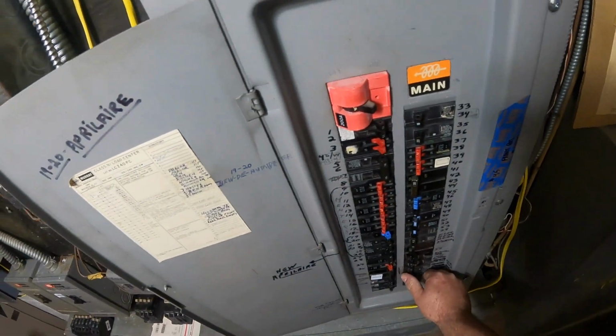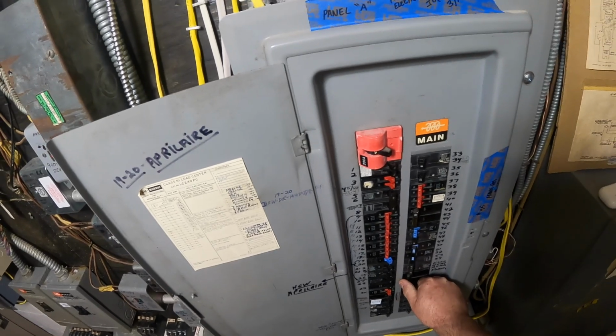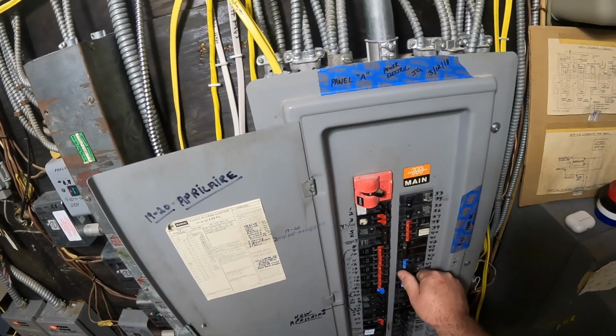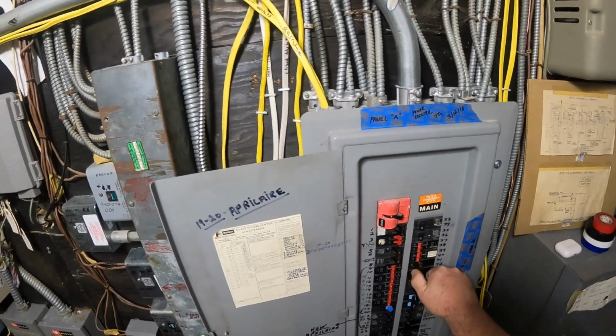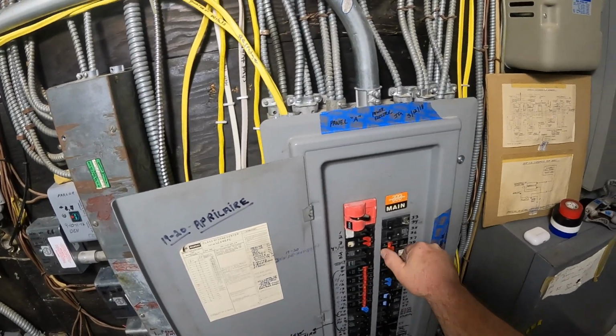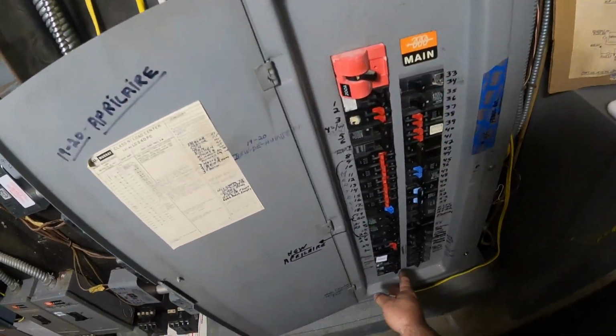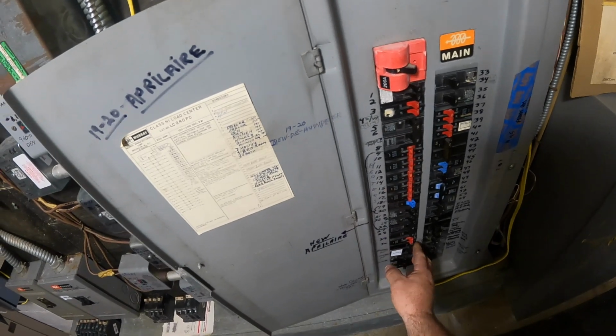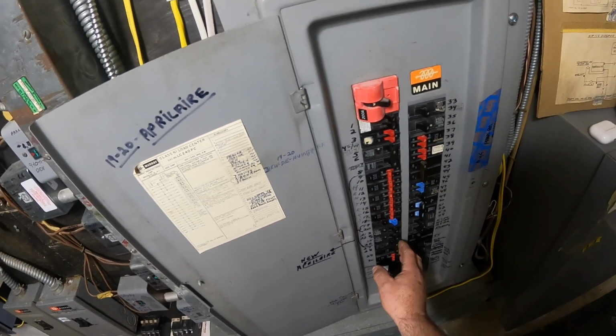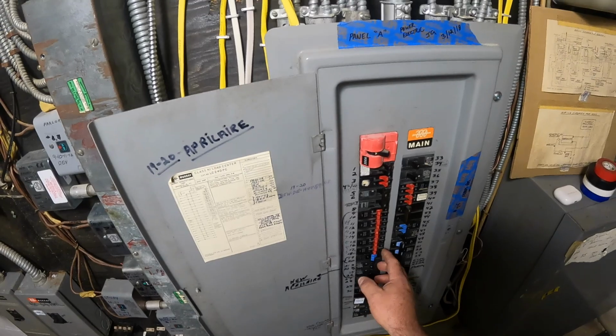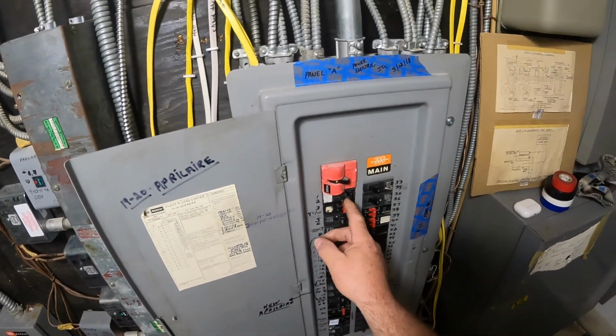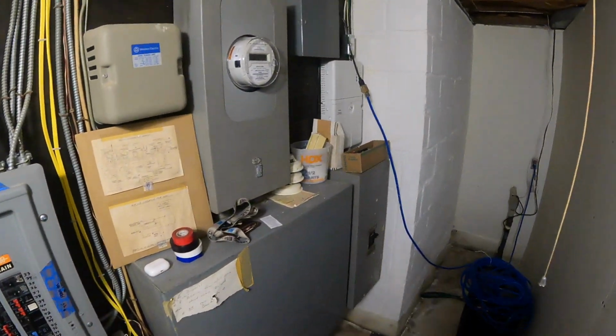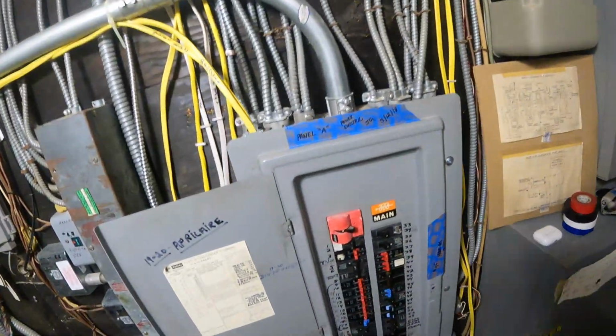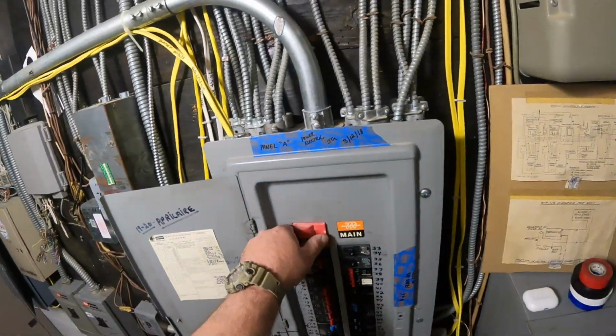The trouble with this panel, as you can see, is there's way too many circuits in a panel that's only rated for 40 or maybe even 30 in this panel. I don't totally remember, but I believe there was about 62 circuits in this panel when it was only rated for 30 or 40. I don't remember the specifics, like I said. So we're here to change out this panel, and that's what we're going to do.